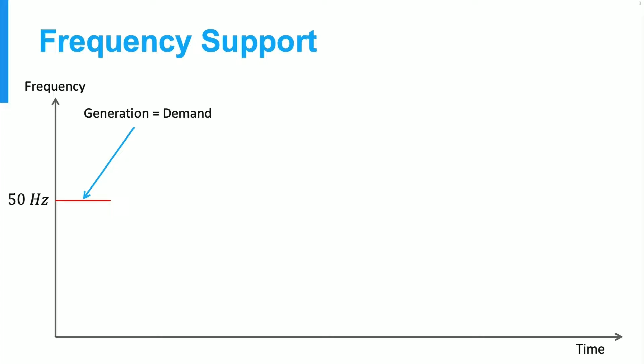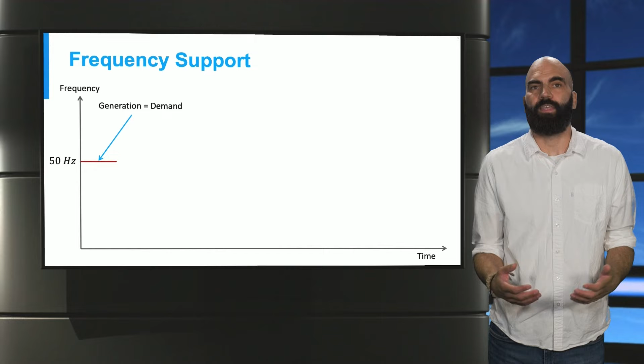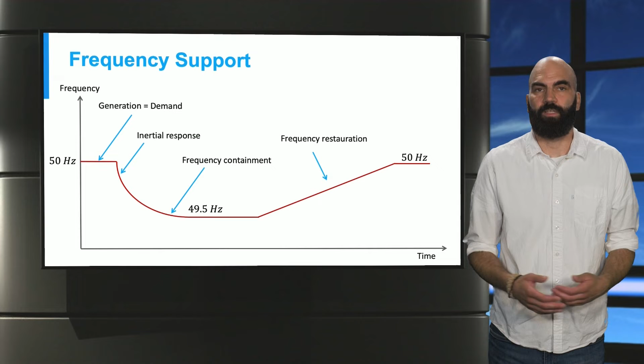The first set of services is related to the support of power system frequency. The frequency is constant when power supply matches power demand and deviates from that value when there are mismatches. To control, maintain, and restore frequency, we can break down the ancillary services into several segments, identifying inertial response reserves, frequency containment reserves, and frequency restoration reserves. We call them reserves since they are reserved to be used when and if they are needed. In this particular case, the provision of frequency restoration reserve is performed through several segments of different size and duration.